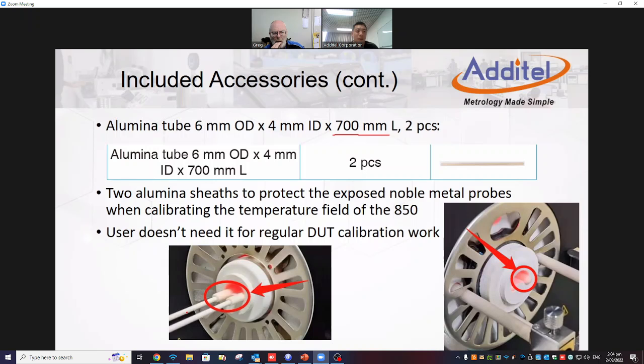This is pretty common. Some lab users need to give their customers a list about the testing accuracy of their lab. So when they do their own test of furnace axial uniformity or stability, they can improve the list numbers. For example, they can use the datasheet specification to calculate their lab ability, but after testing they find that the 850 has better performance, so they can improve their service sheet about the accuracy of their service. So we do recommend the customer to test the uniformity and the stability once they receive the furnace.